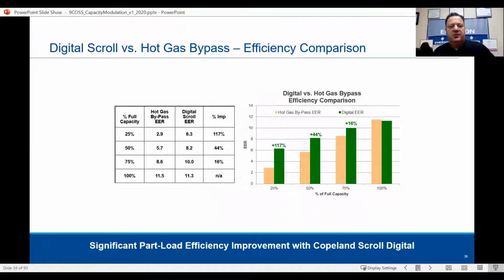So let's take a look at some of the benefits of digital. This is just a digital scroll versus hot gas bypass efficiency comparison. Now, granted, hot gas bypass is not known for being extremely efficient, obviously, but let's just see, because it seems to be way more common in refrigeration than digital is as of now. So let's look. We have our capacities over here on the left-hand side: 25%, 50%, 75%, 100%. We have the comparison of hot gas bypass EER and the digital scroll EER, and then our percentage of improvement.